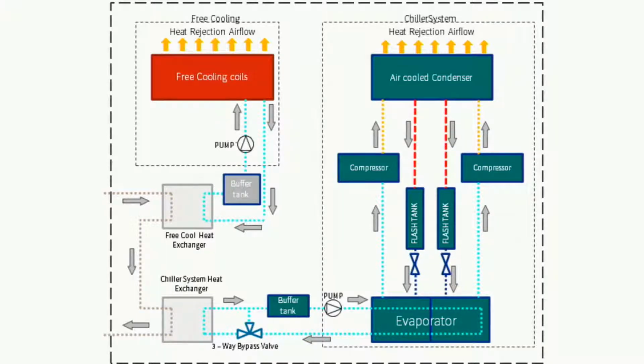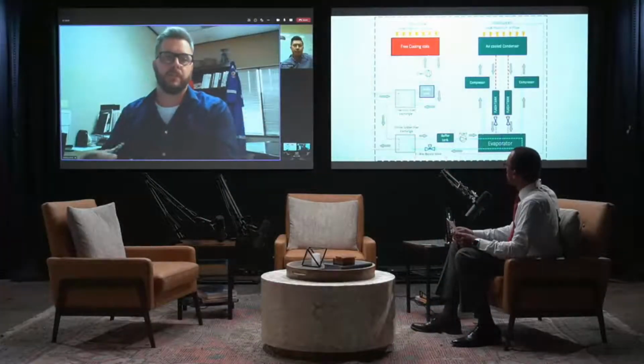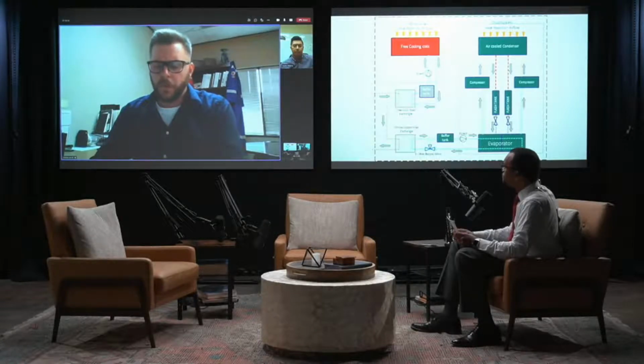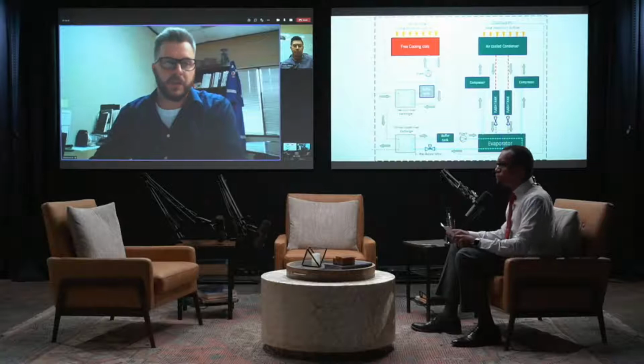The higher the ambient temperatures, the less efficient it works. That's actually where we have a patent pending for the controls, to knock off that stage 1 when it's not actually doing anything effective to the mud. If the ambient temperature is higher than the drilling fluid that's entering that stage, it will disengage stage 1, and you won't be doing the reverse effect of heating the drilling fluid. That's really unique to us and to our unit with that first stage.